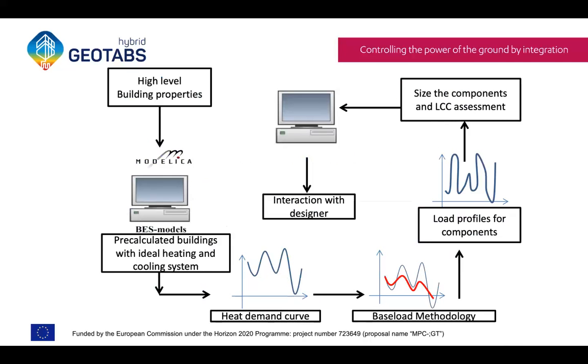What it does is it takes a number of high-level building properties, and based on these, it selects from a pool of pre-calculated buildings an ideal heating and cooling curve for that system. Then it applies what we call a splitting algorithm, which I'll discuss later, to assign part of the load to the GEOTABS system and another part to the secondary system. Based on those split load profiles, we can then proceed to size the different components for the TABS and the secondary system, and provide that as feedback to the designer for informing the decision making about the selection of the system.